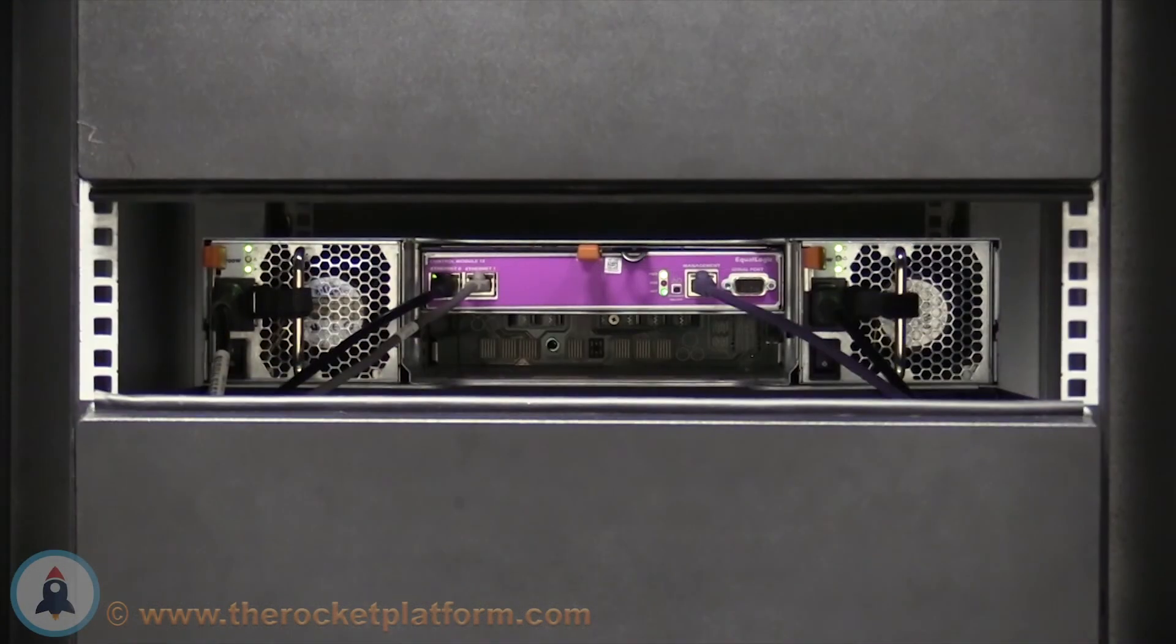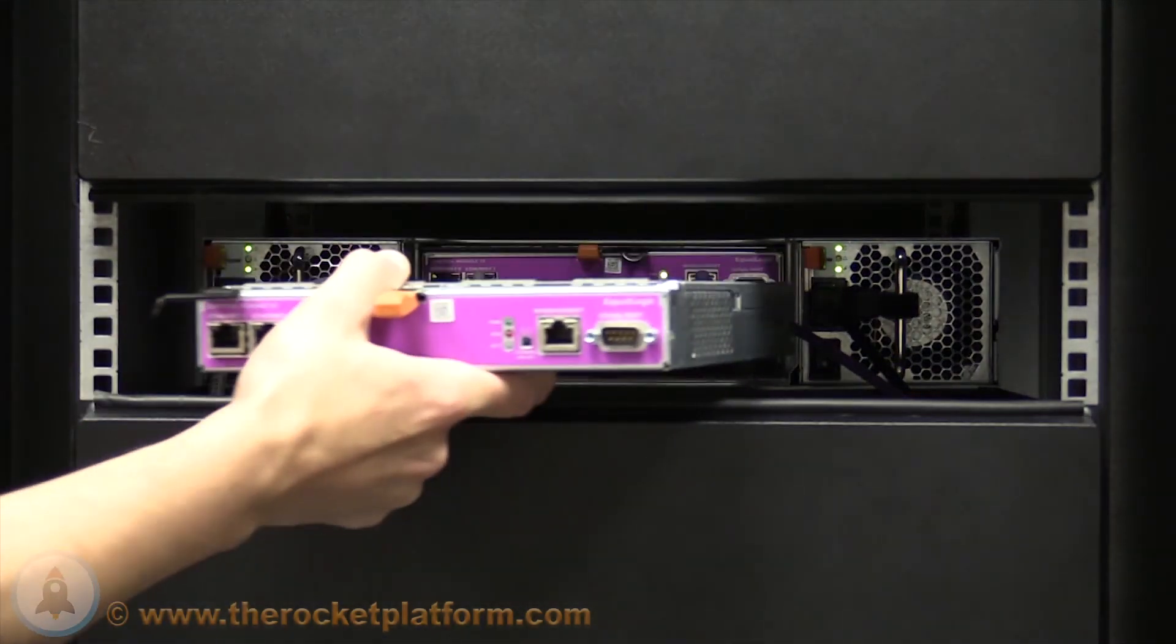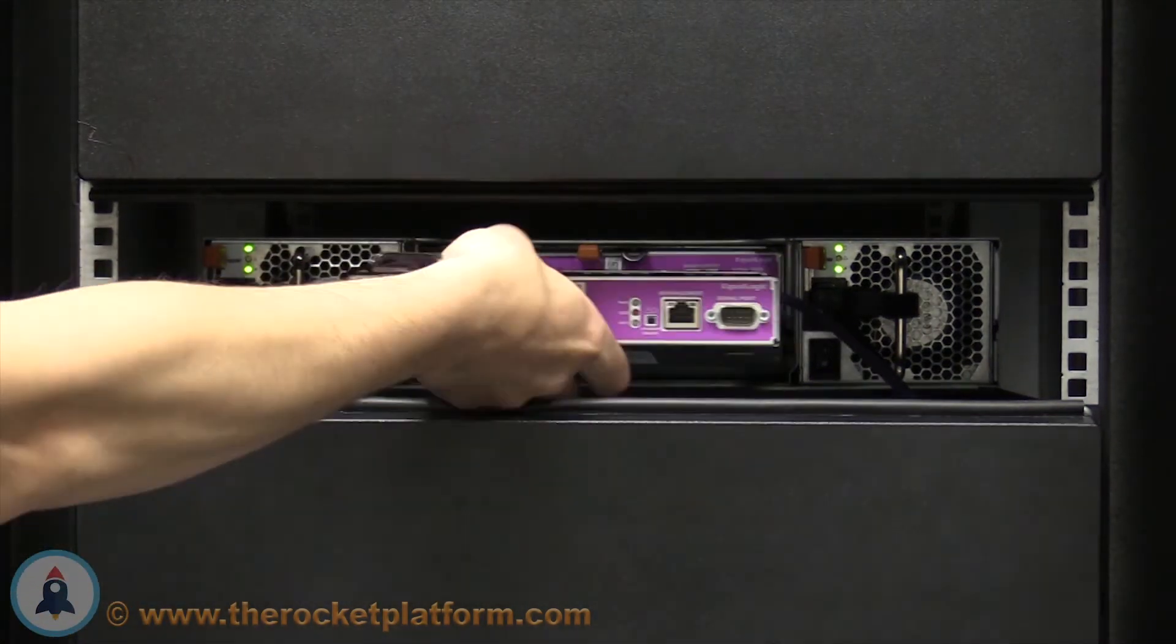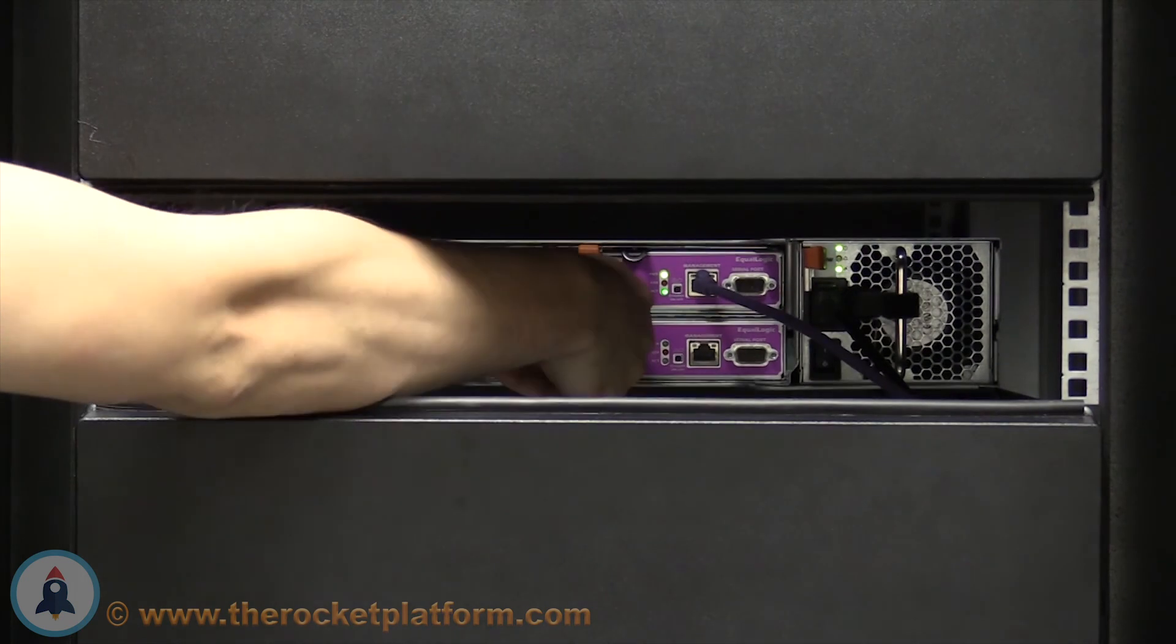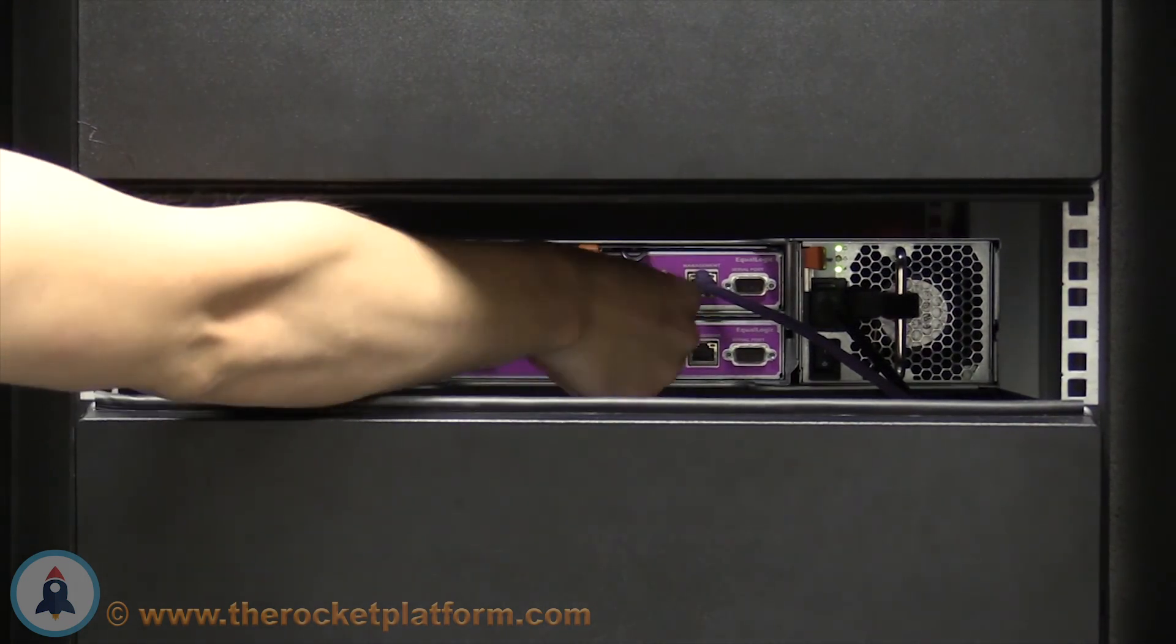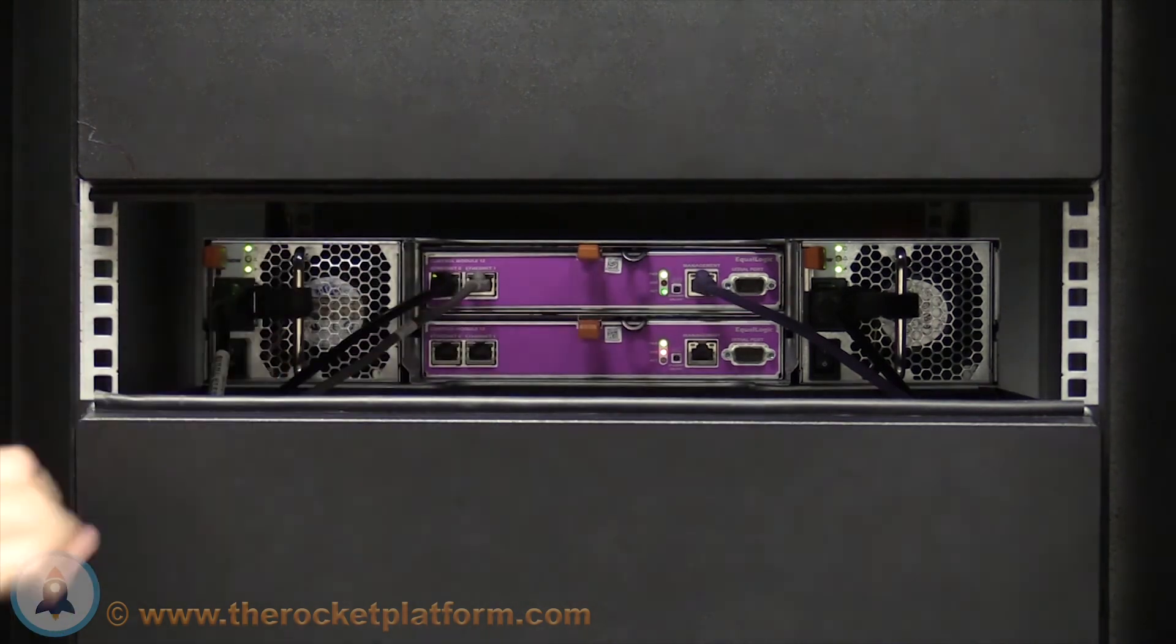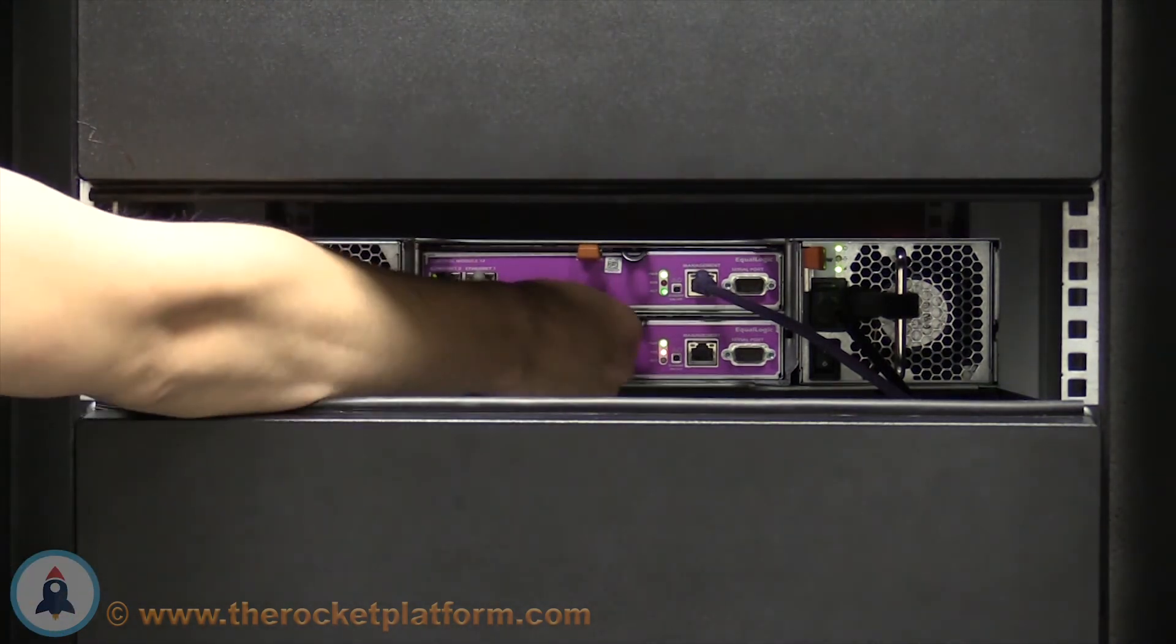Open the lever all the way on the replacement controller, then insert it into the slot. Once seated in around 90% of the way, the lever on the controller will begin to catch. Once the lever begins to catch, push the lever inwards until you see or hear the orange tab click into place.